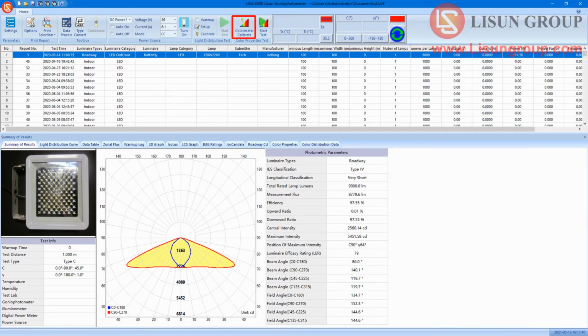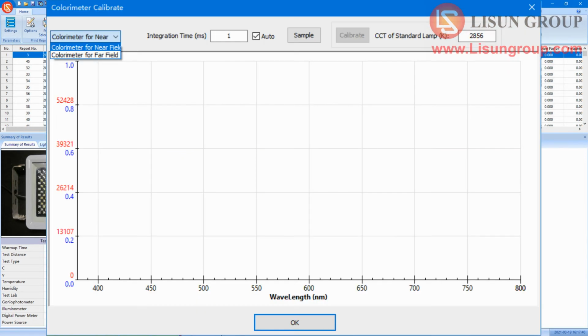Click Colorimeter Calibrate. Choose colorimeter for near field. Always check auto for the integration time. Click Sample. After successful sample, the Calibrate button will be available. Input the correct color temperature of the standard lamp, and click Calibrate. Click OK after successful calibration.